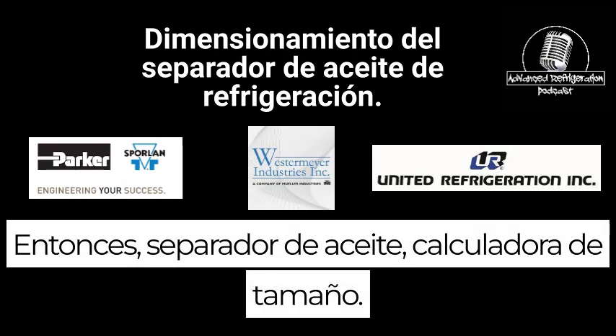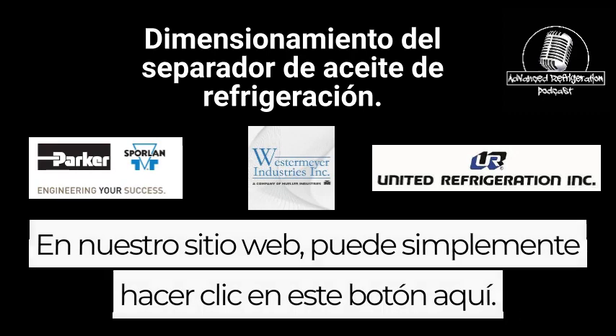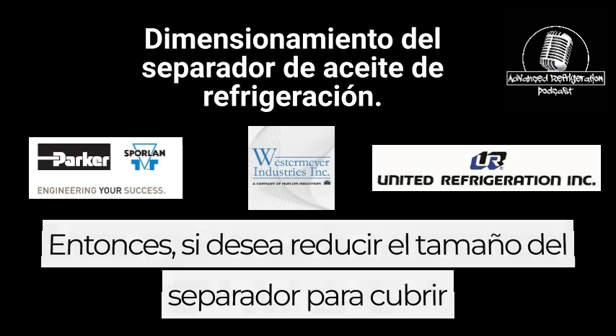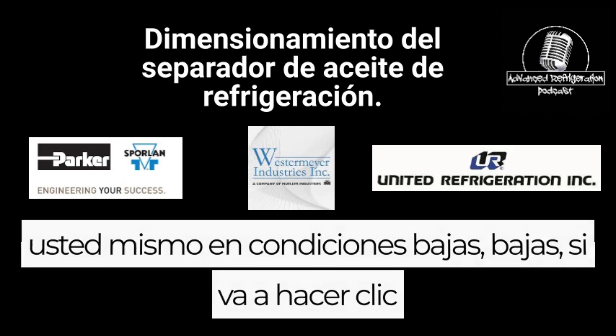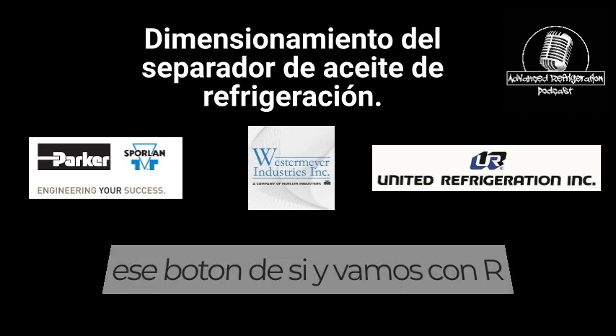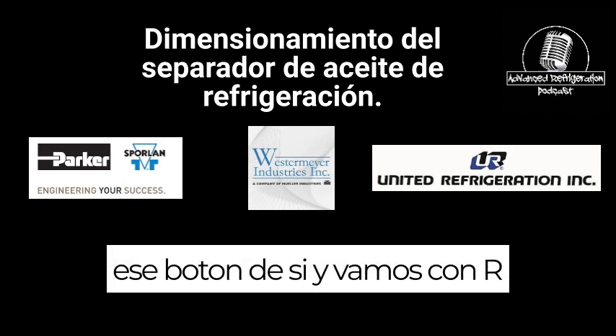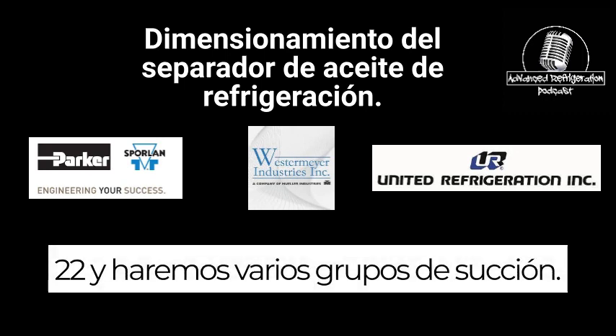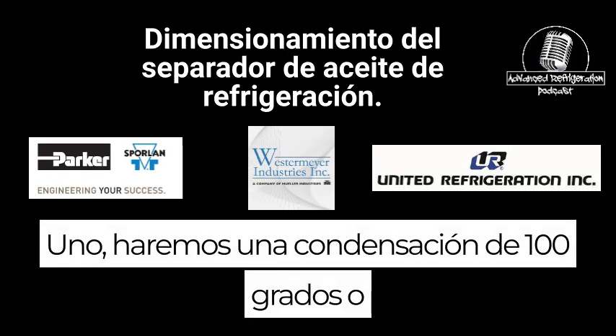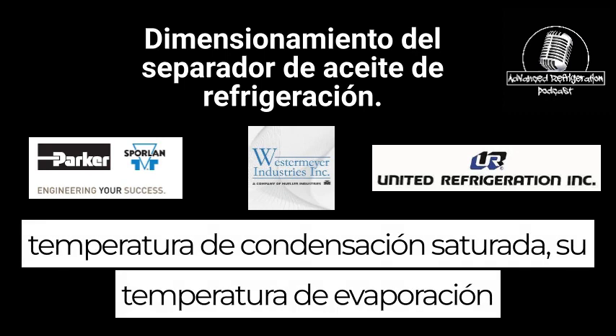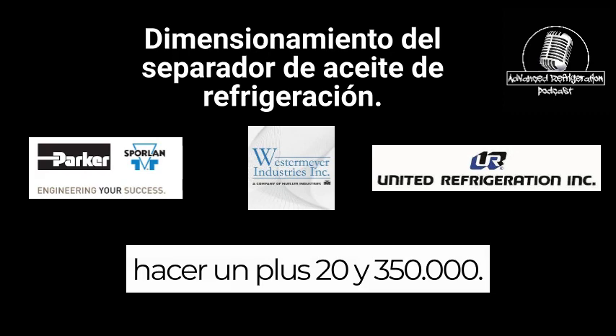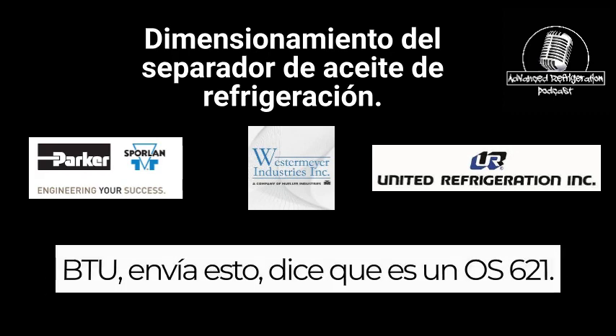So, oil separator sizing calculator on our website, you can just click this button here. If you're wanting to undersize the separator to cover yourself on low conditions, you click that yes button, and we're going to go with R22, and we'll do number of suction groups 1. We'll do 100-degree condensing or saturated condensing temperature. Your evaporating temperature, we'll do a plus 20 and 350,000 BTUs.